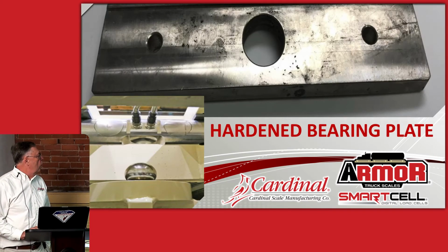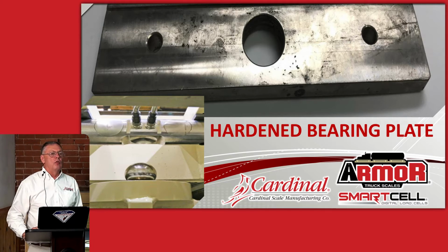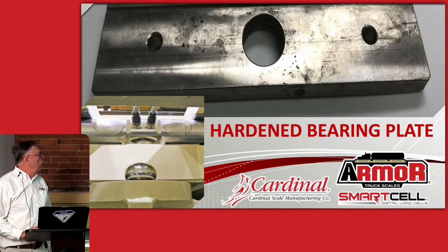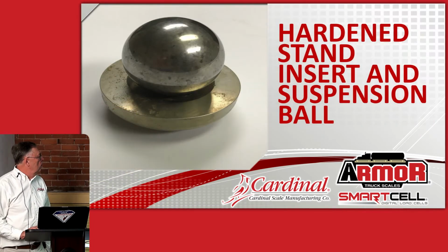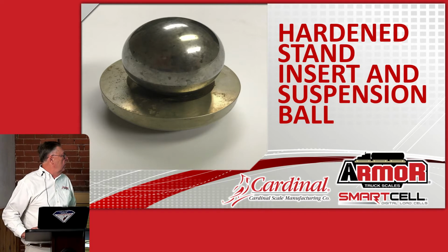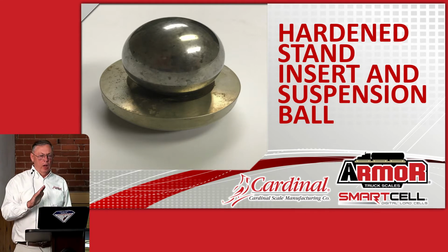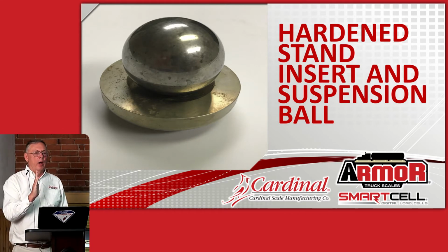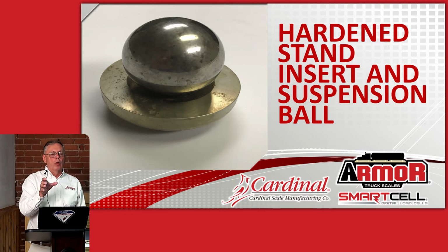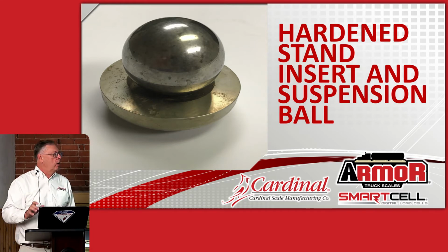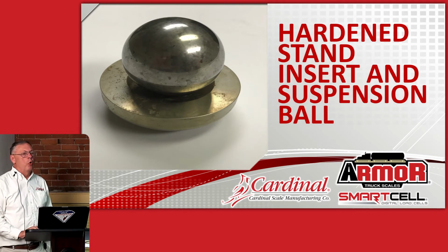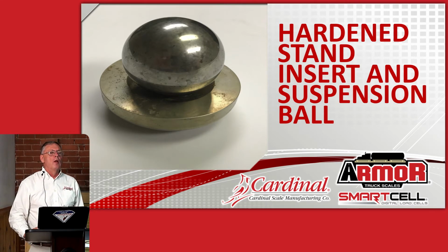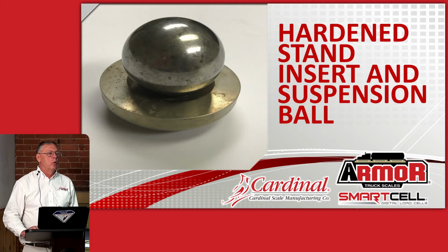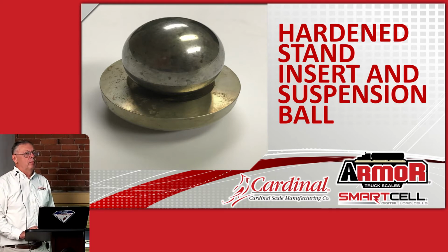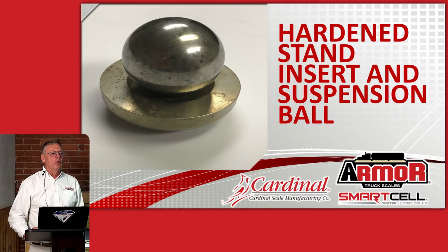This is a photograph of the hardened steel plate that's installed between the load cell and the weighbridge. And this is a hardened stand insert and suspension ball. The bottom of the insert has a radius on it so that if the stand is a little bit out of parallel, the insert can actually straighten itself up in the stand. Almost no parts; those are the only 2 parts that should ever be replaced in one of the new ARMOR truck scales. And it would take basically 5 minutes to go in and put a new set of them in there.